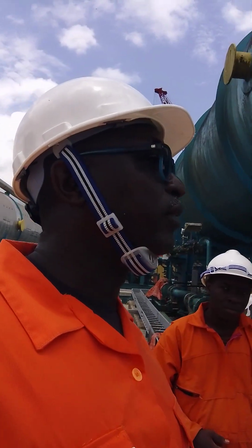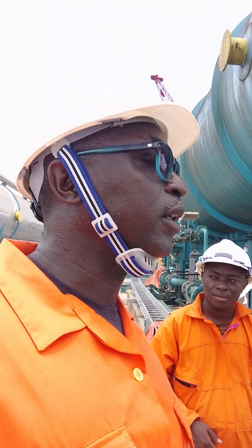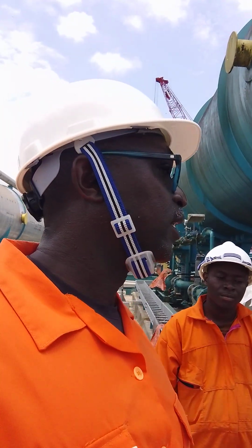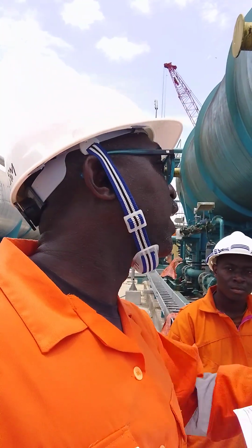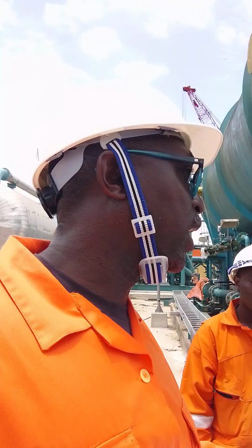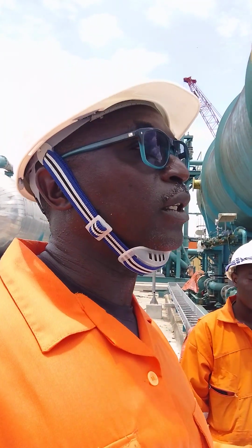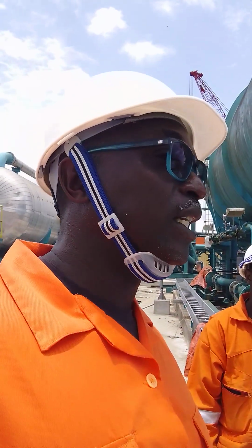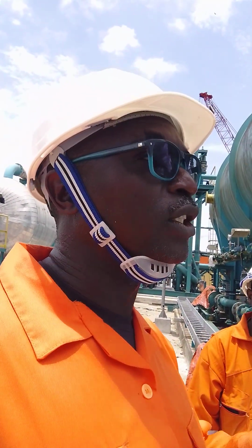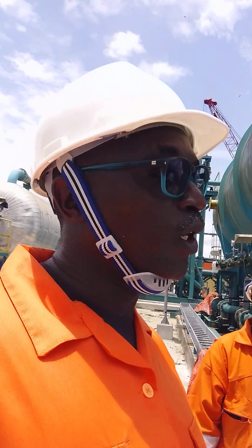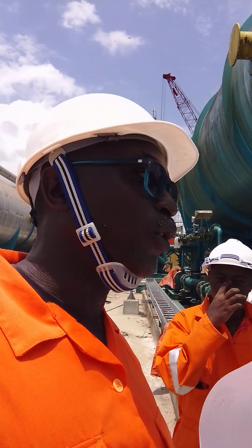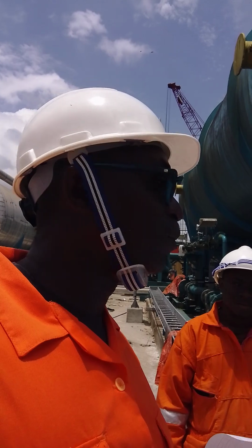For instance, you have a crude processing plant. The P&ID shows you how the entire plant is integrated. One equipment moves from one point to the other, how it joins the other. Compared to an isometric drawing that tells you how a particular section of the pipe is moving from one point, from one coordinate to the other. Remember, the P&IDs do not respect coordinates. They don't have any business with coordinates.